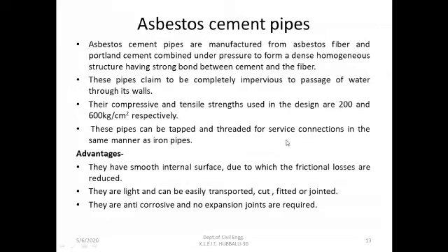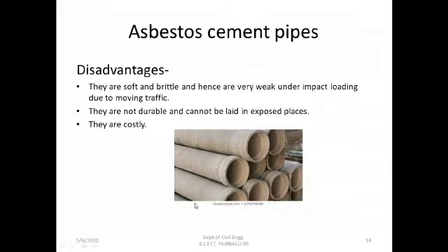These pipes can be tapped and threaded for service connections in the same manner as iron pipes, and they have a smooth internal surface due to which frictional losses are low. They are light and can be easily transported, cut, fitted or jointed. They are anti-corrosive and no expansion joints are required here as well.